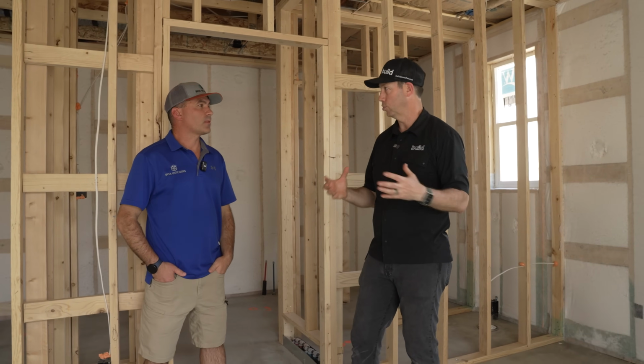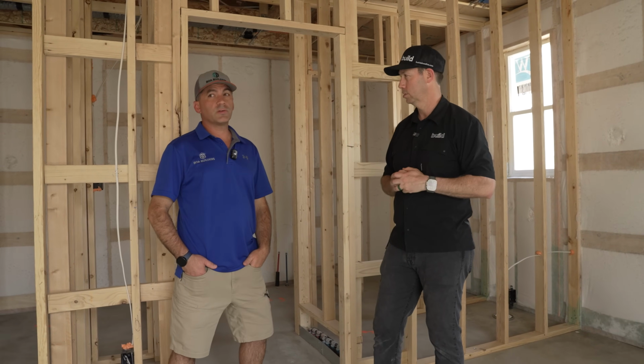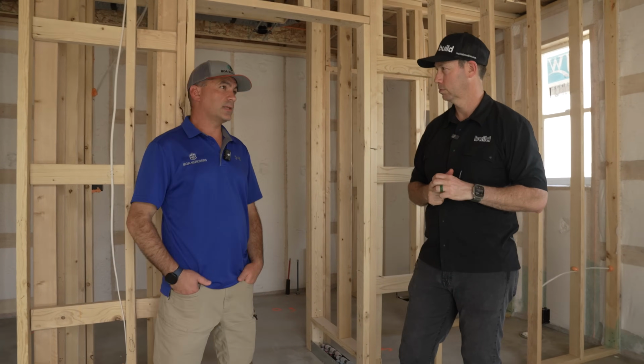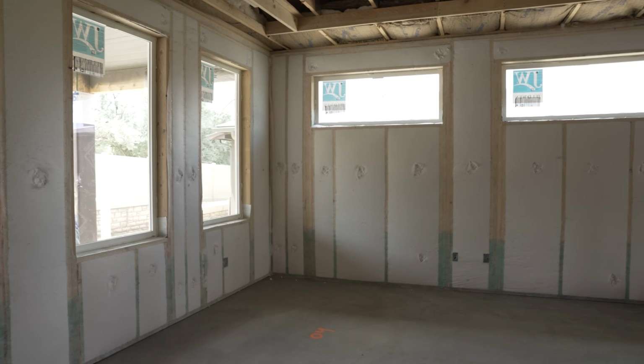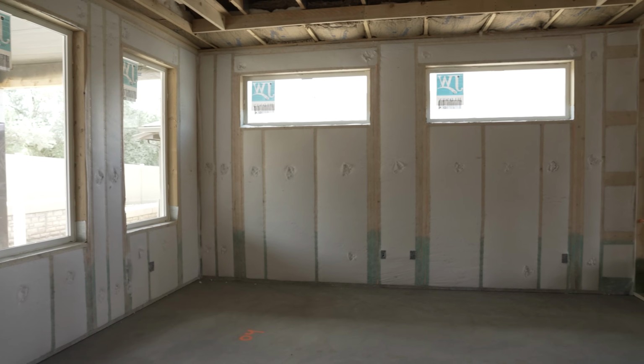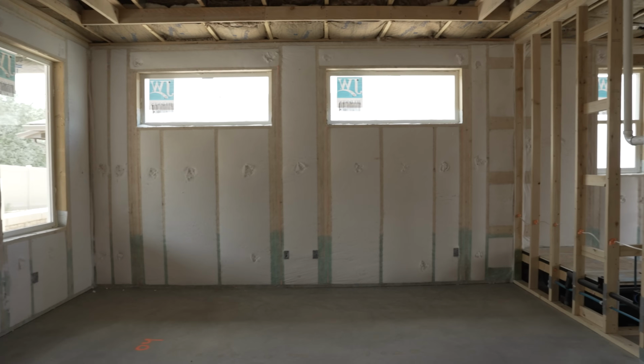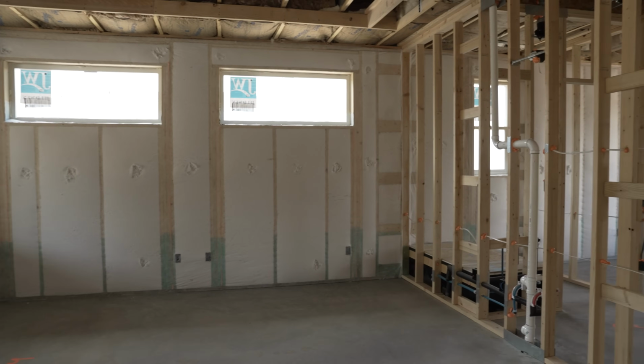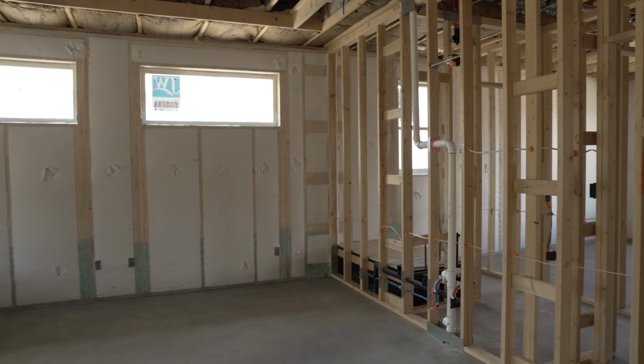What are your general load calc numbers for a house like this? For this size, 1,500 to 1,800 square feet, we're usually at a 2-ton unit, for both heating and cooling. That's not bad at all, 2 tons of heating, that's like 900 square feet per ton for heating and cooling. Pretty good.